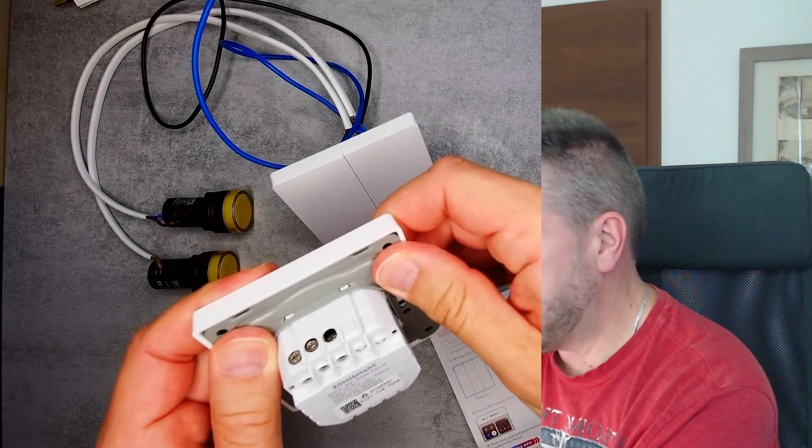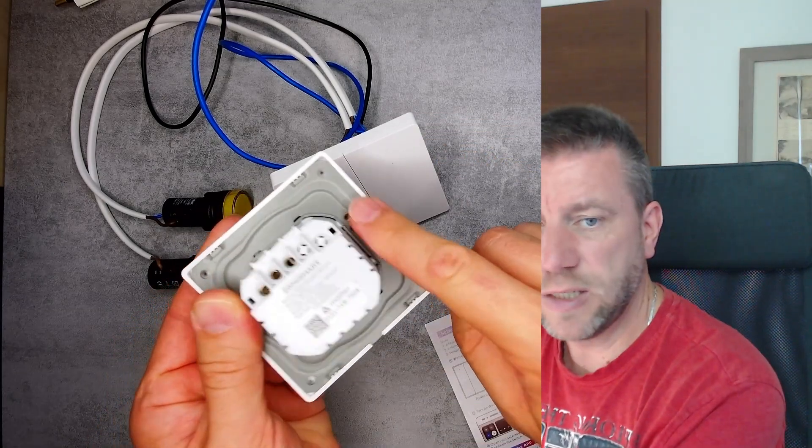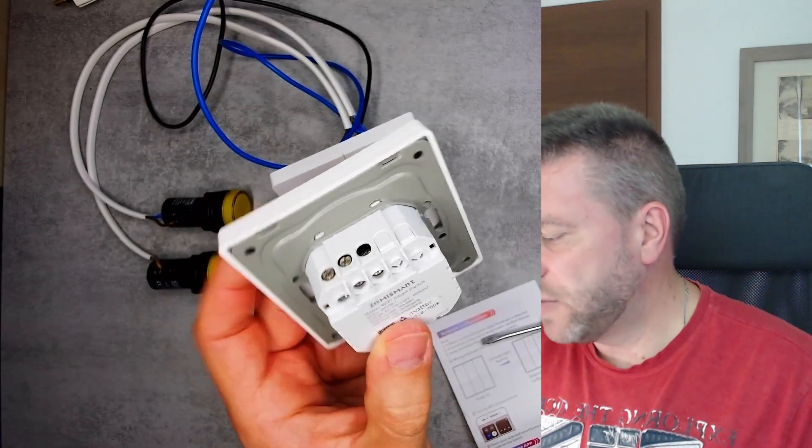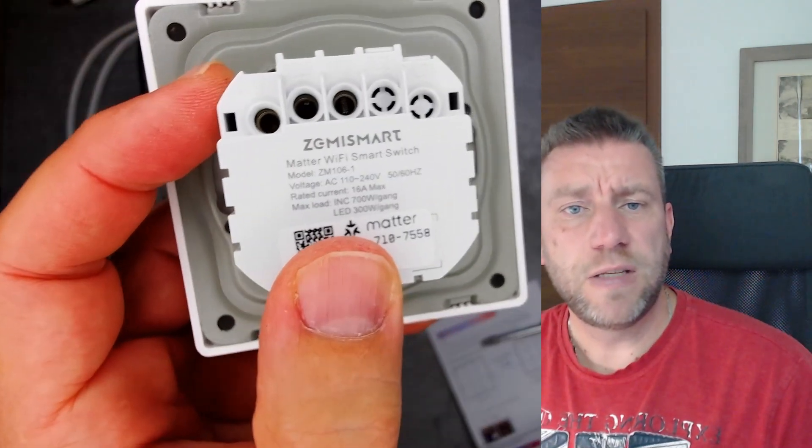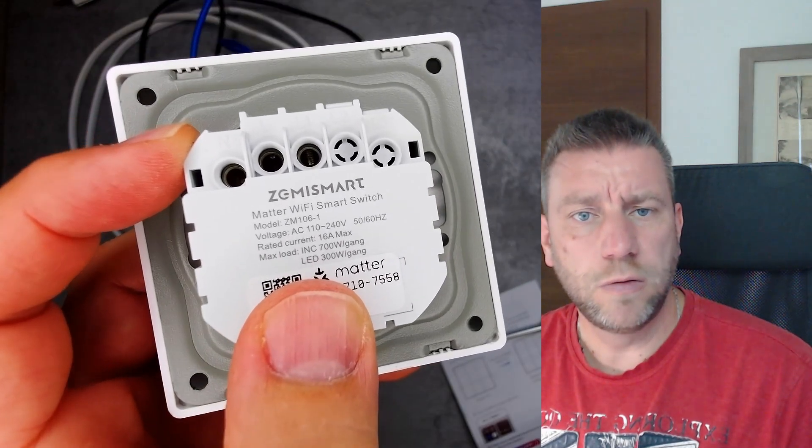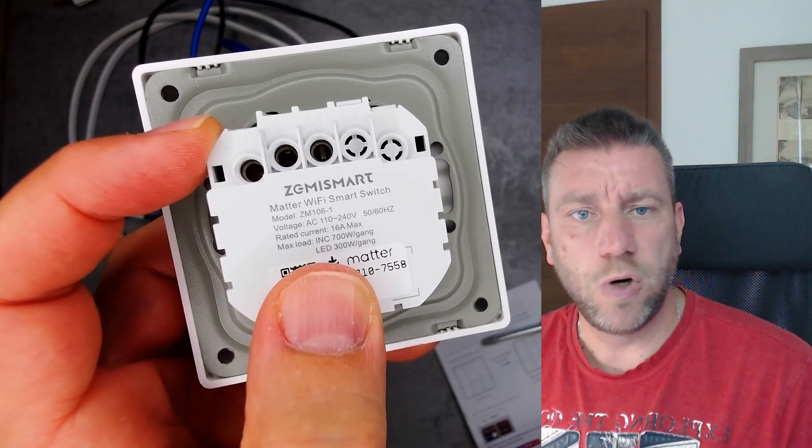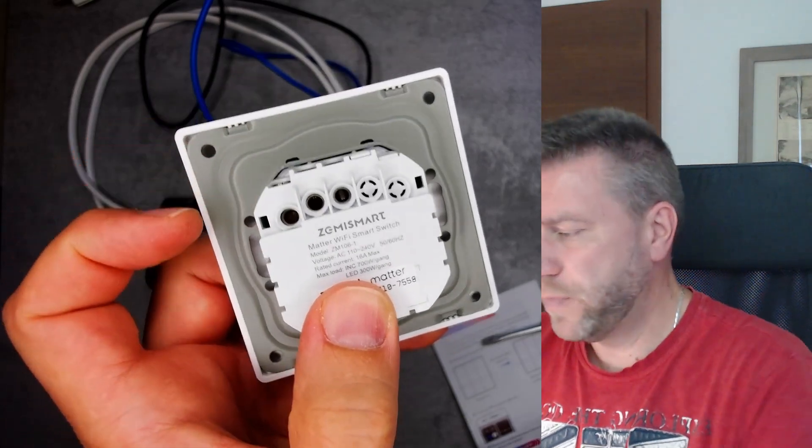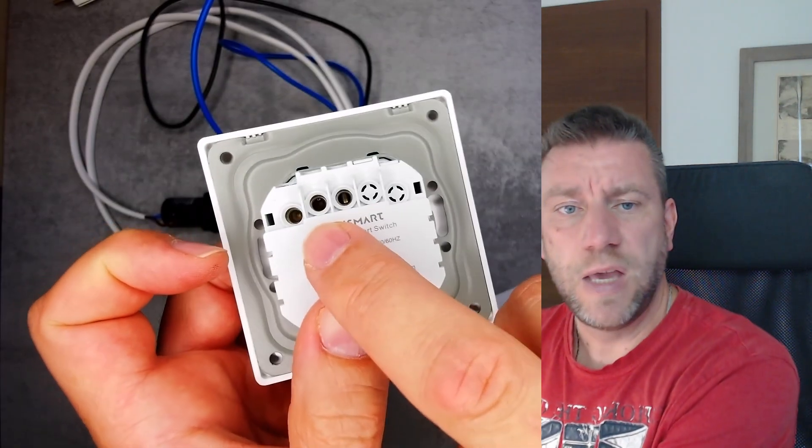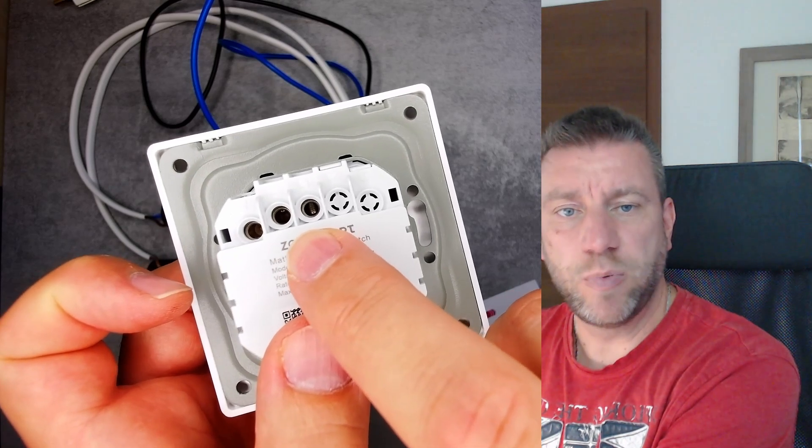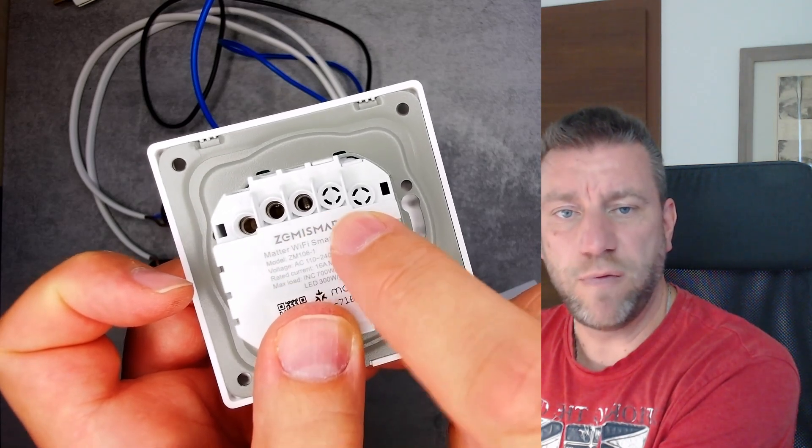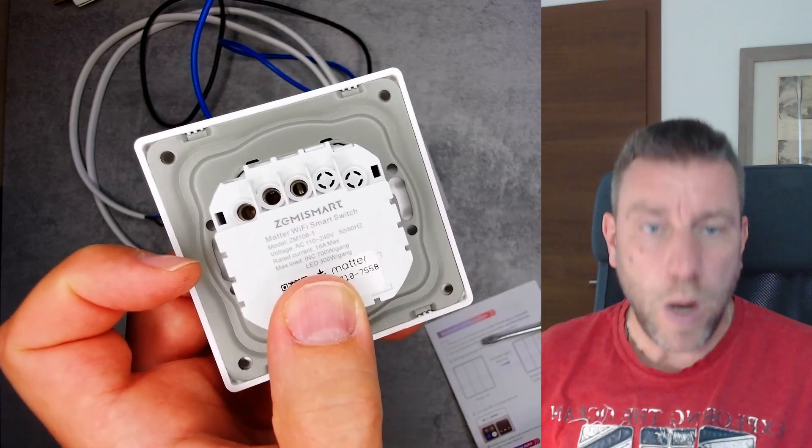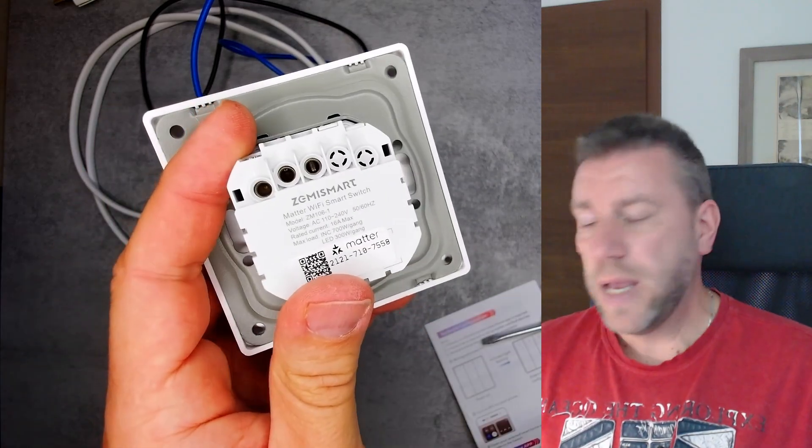In terms of the wiring, it's very simple. So you have the neutral, you can't really see that but that's the neutral, and you have live, that's the next connection. So the second one is live, and then everything right to that are the outputs. So live one, live two, and live three. Obviously it only has live one L1 because it's a one-gang switch.